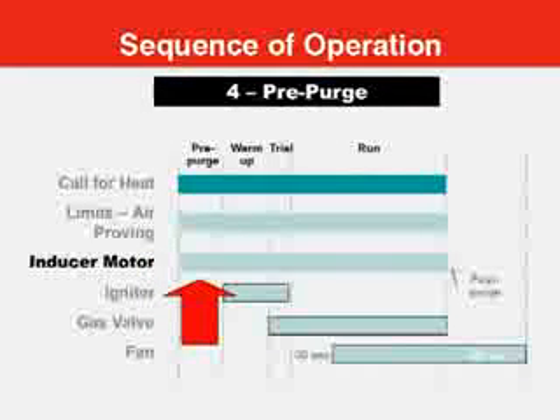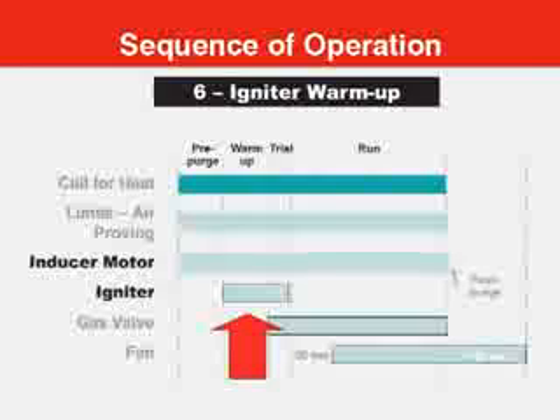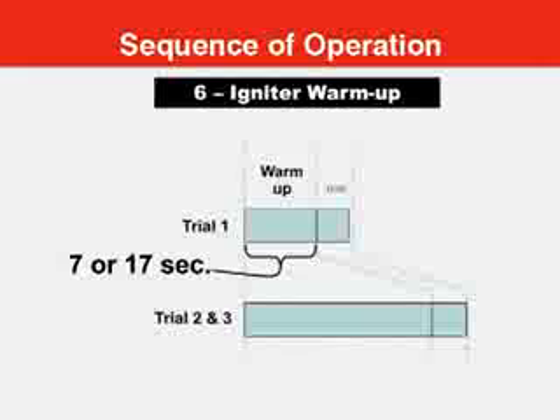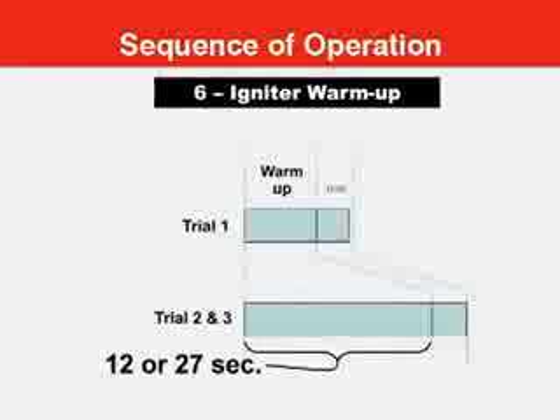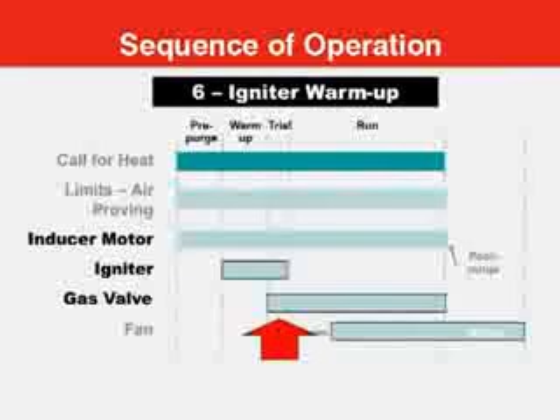At that point, a 30-second pre-purge starts, after which the hot surface igniter is turned on. The installer chooses the HSI warm-up period to best match the igniter on the furnace, 7 or 17 seconds. It provides a longer igniter warm-up on the second and third trials for ignition, 12 or 27 seconds. So if it doesn't light on the first try, the igniter is given a little longer to warm up so it gets a little hotter for subsequent tries. Now the gas valve is opened and the trial for ignition is started. Depending on what the installer has set, the trial lasts either 4 or 8 seconds.